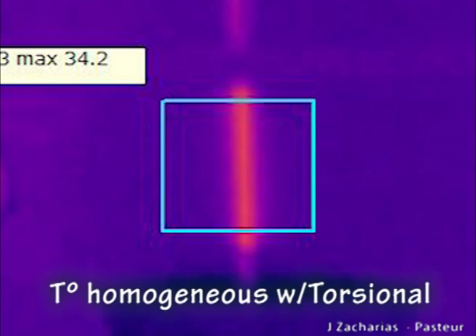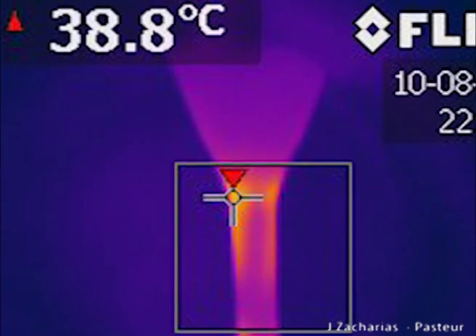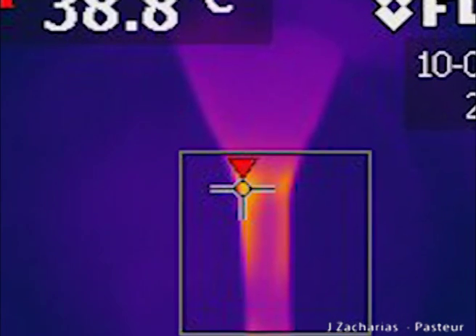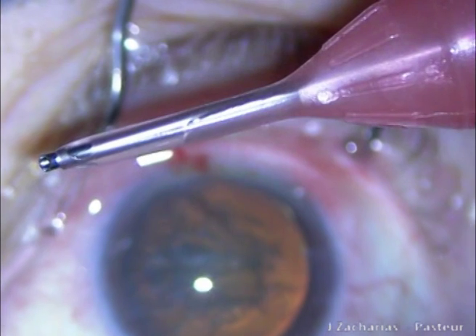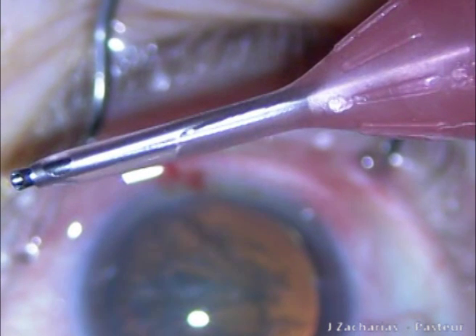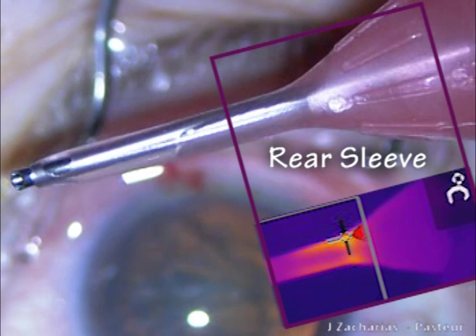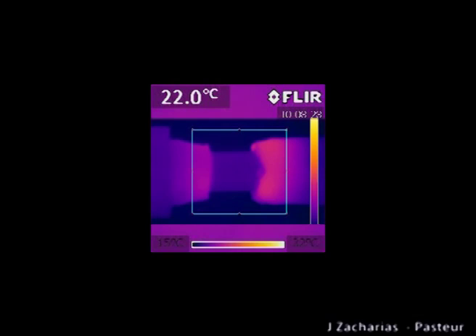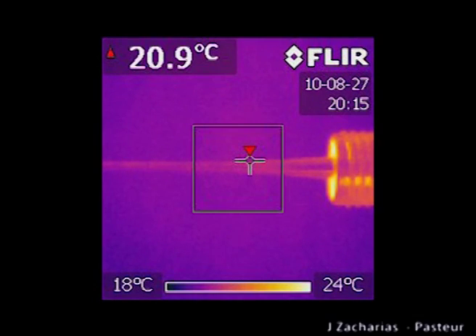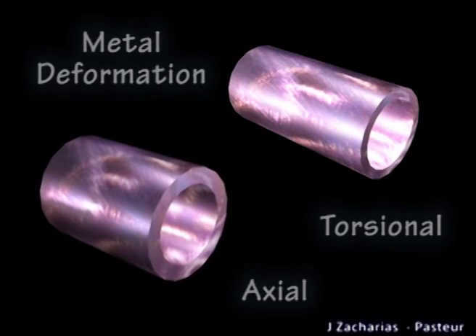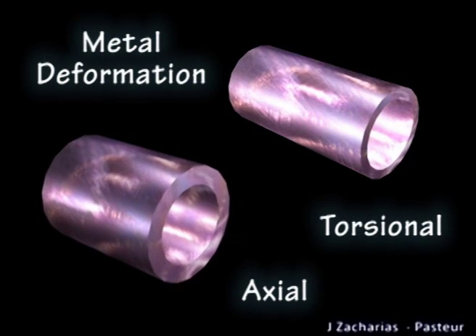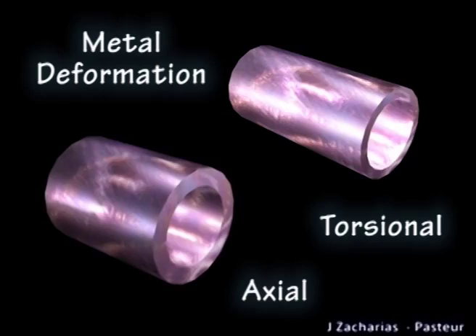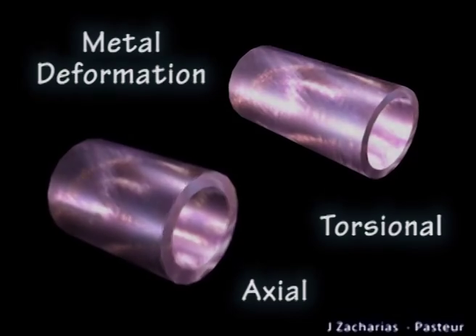No focal temperature increase was found in the shaft of the probes that could correlate with the warm zones observed at the back of the sleeve in torsional mode. These warm zones, with no reported clinical relevance, could be related to some polymer response to the acoustic field, but not to probe self-heating. Internal metal stress, if involved, would be more relevant in axial mode according to these tests.